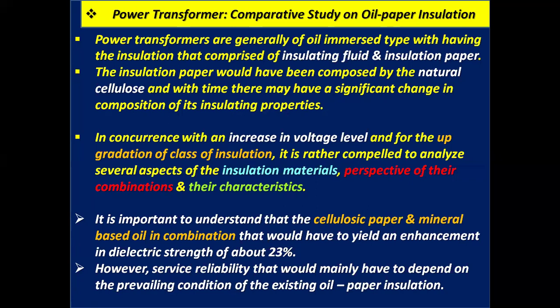In concurrence with an increase in voltage level and for the upgradation of the class of insulation, it is necessary to analyze several aspects of the insulation materials, their combination and their characteristics. It is important to understand that cellulosic paper and mineral based oil in combination yield an enhancement in dielectric strength of about 23%. However, service reliability mainly depends on the prevailing condition of the existing oil paper insulation.